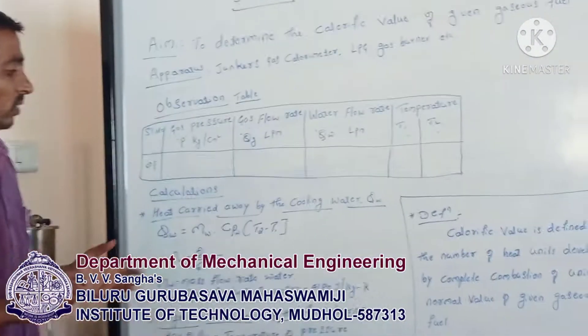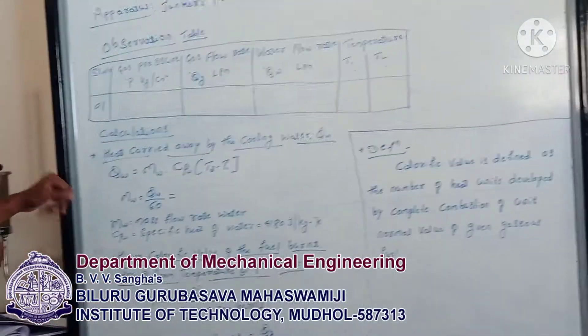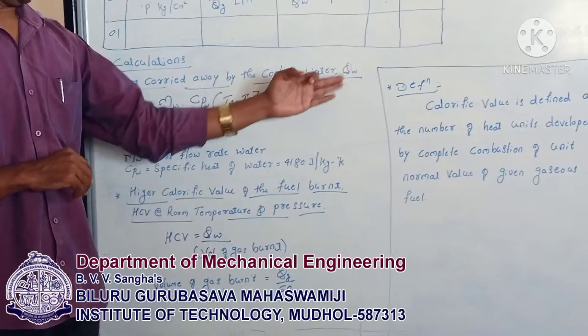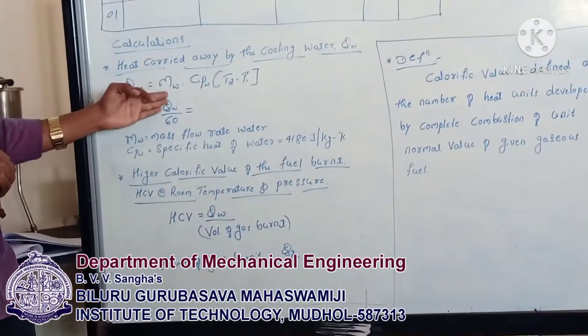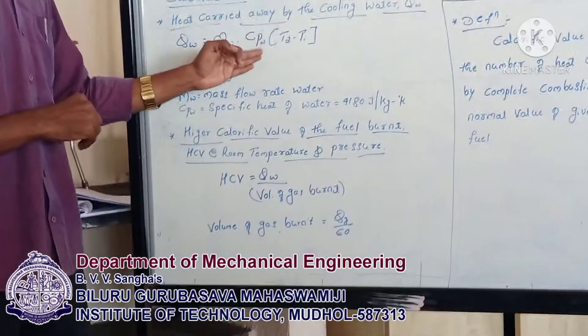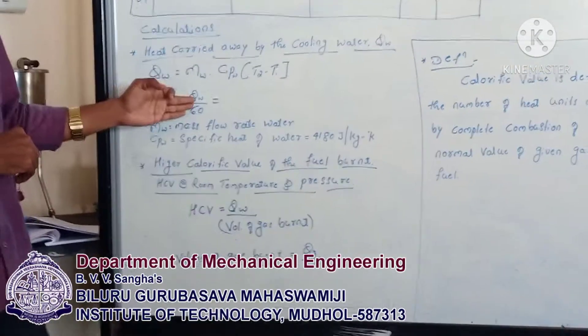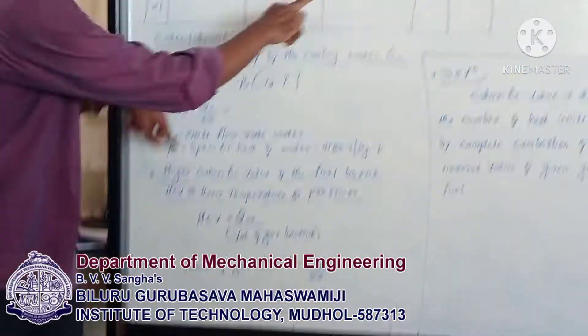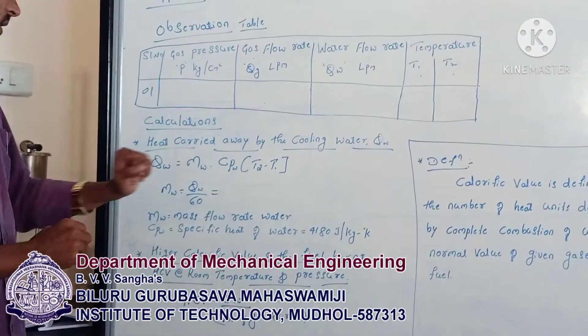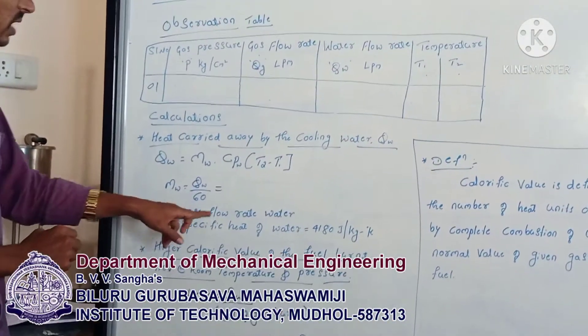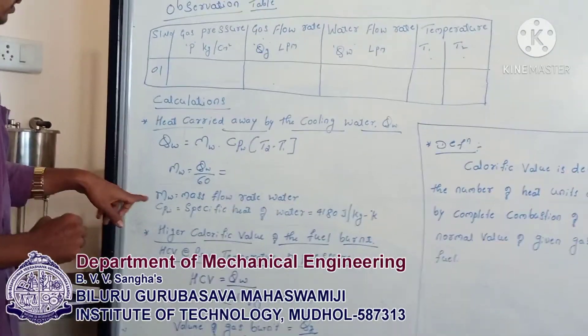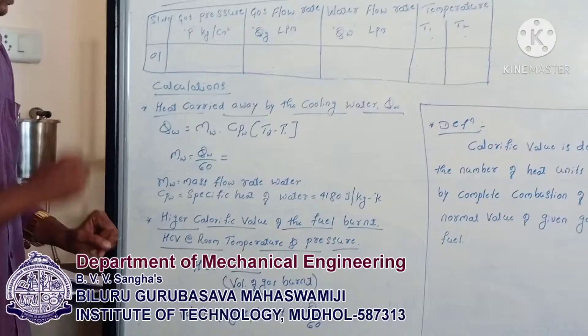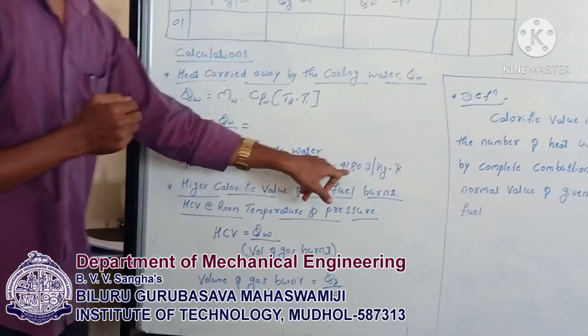Calculation. What is the formula? The first one is heat carried away by the cooling water, which is Qw. Qw is equal to Mw multiplied by Cpw multiplied by (T2 minus T1). The Mw is the water flow rate divided by 60. Mw means the mass flow rate of water. Cpw is the specific heat of water, which is 4.2 — it is a constant value.